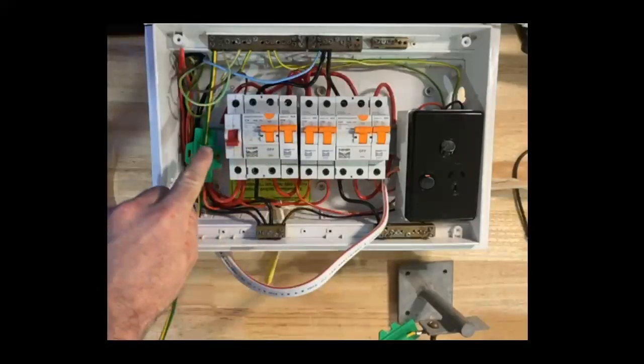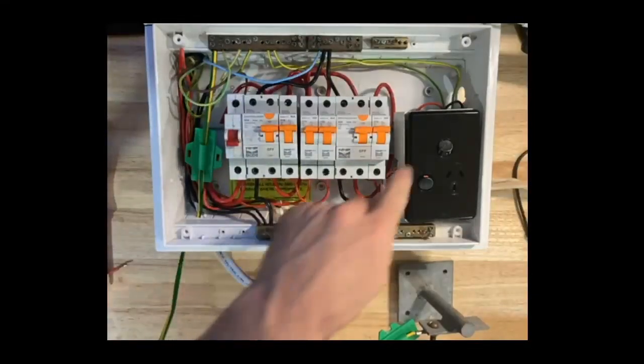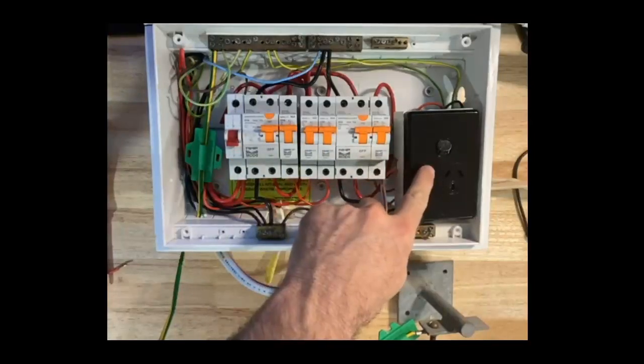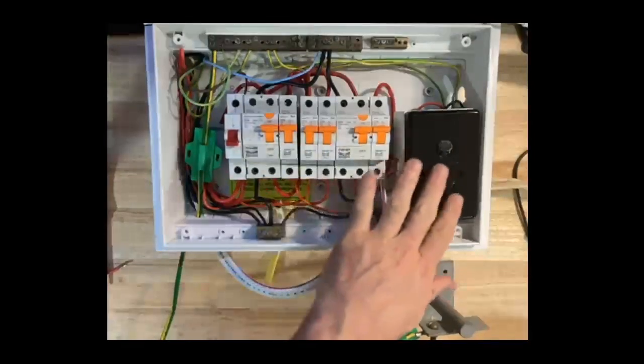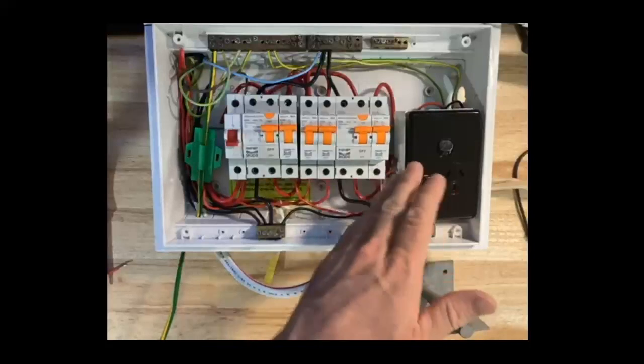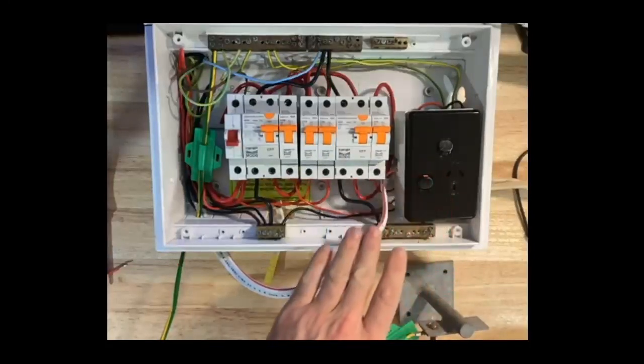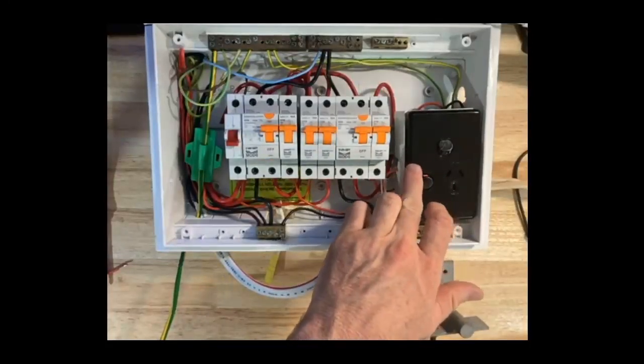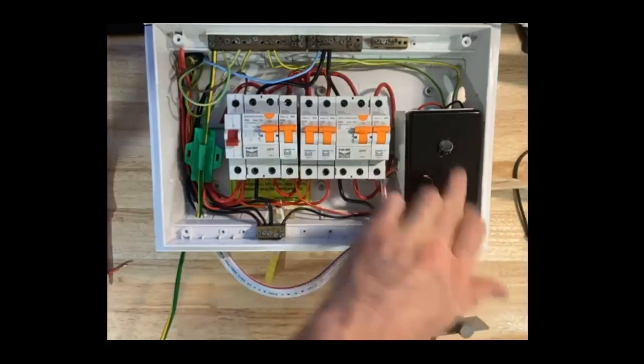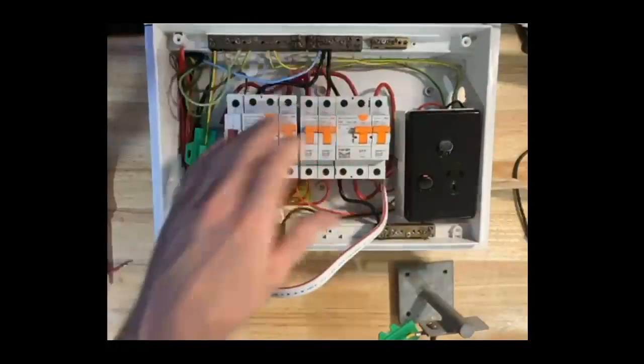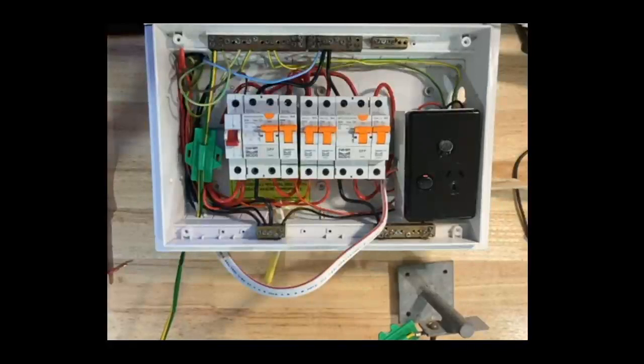what value of resistance is allowable in the earthing conductor running from my socket in this case, or it could be a lighting circuit or whatever you've got in your installation. And remember, we must test every sub-circuit in the installation. So the maximum value of the earth conductor between here back to the earth bus bar is given in table 8.2, and we will look at that shortly.